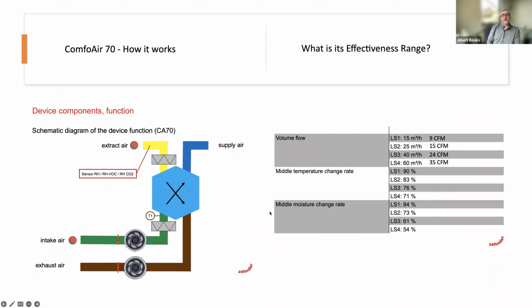Here's how that little device works. In the middle, that blue eight-sided figure is the core, and it's got two arrows. That's the airflow, one flowing up and one flowing down. And so when we mount it inside, we see that the green arrow lower left and the brown line are essentially the outdoor connections, right? Those little fans down there in the lower lines are just parked right next to the outdoors. They're always running 24/7, and they're running at a controlled airflow. And we can run them at 4 different speeds, and those 4 different speeds are listed on that right-hand graph. But just hang with me for a minute.